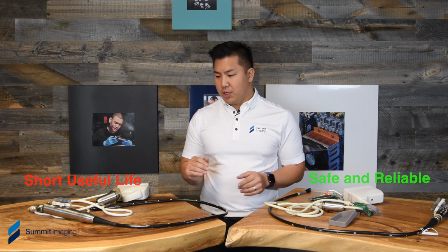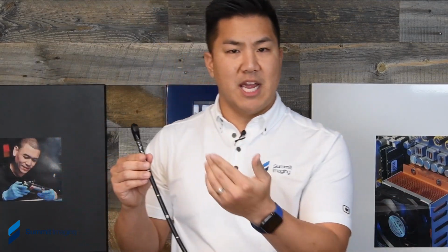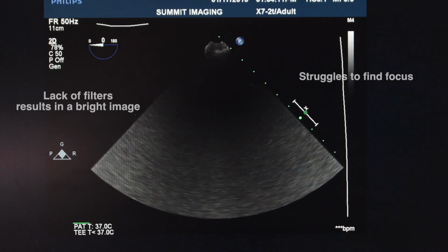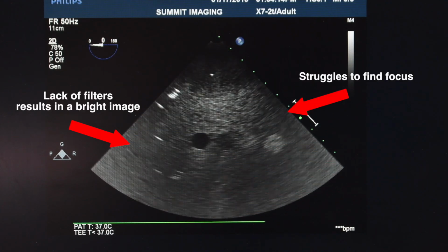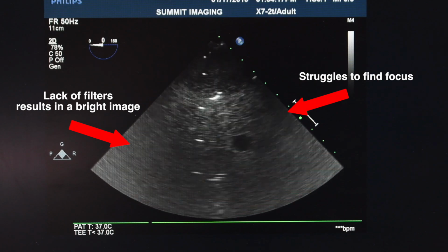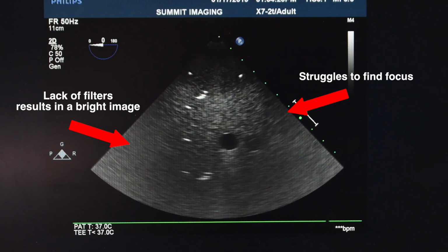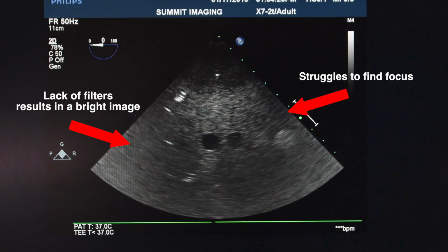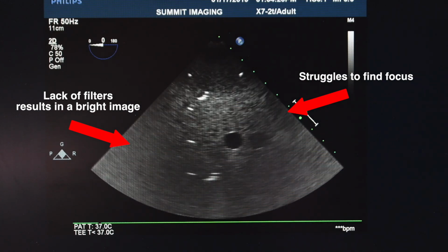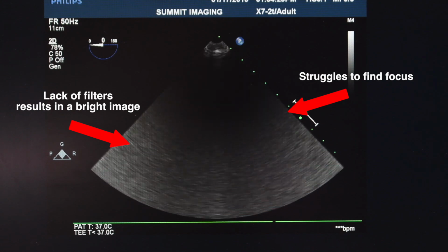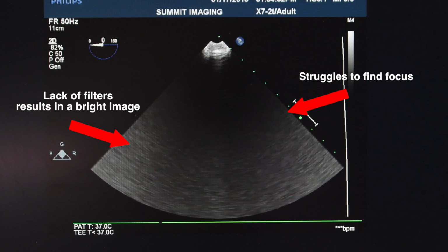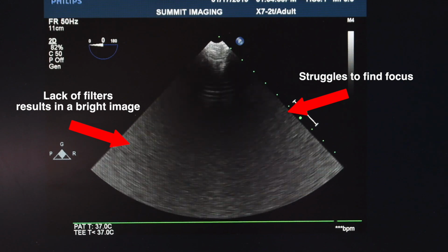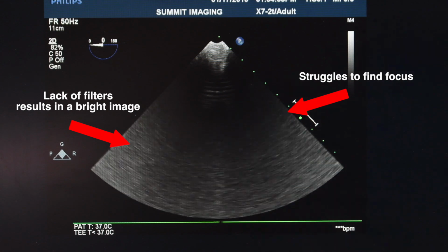Now the other two things we want to chat about today is, number one, the lens as well. This lens, we'll show you examples of how it is really interfering with the image quality of the transducer. If you look at the image that we're showing you right now, it's extraordinarily bright and it's lacking some of that. This is just an image quality assessment that it's too bright, and we are assuming that there are no filters in there. And there are some materials inside that help with the image quality, and it looks like that is missing.